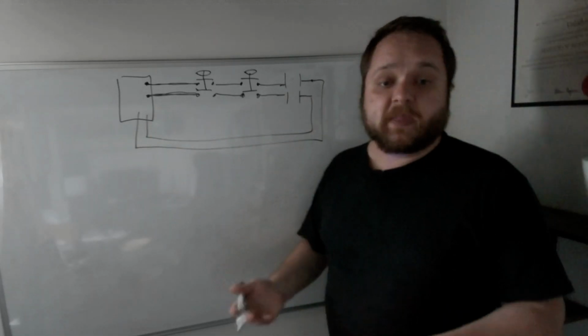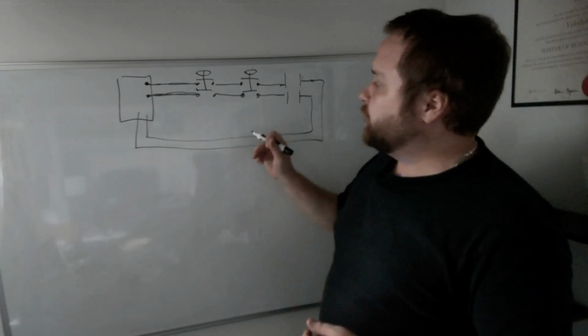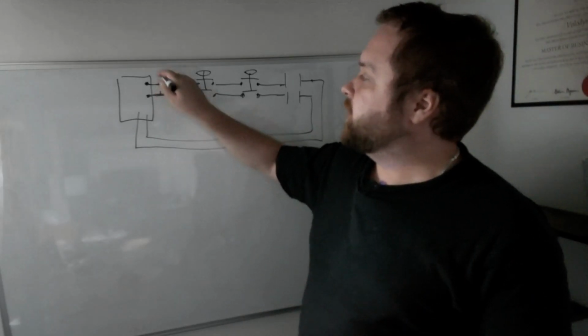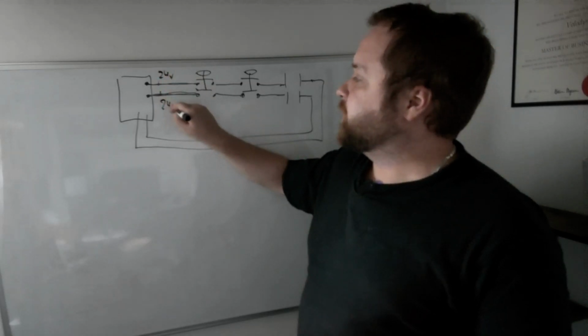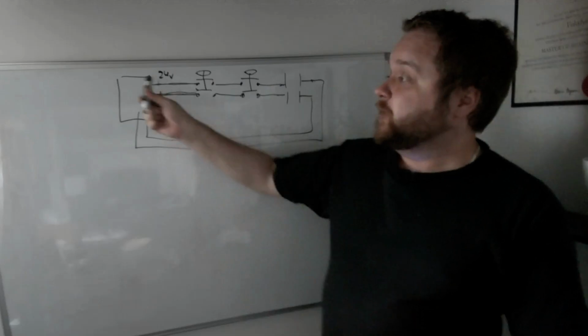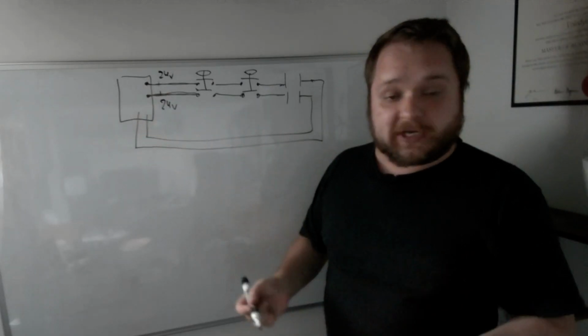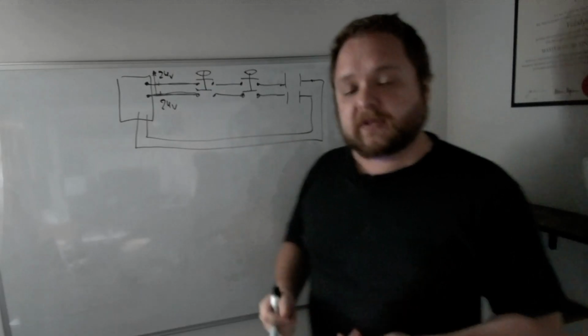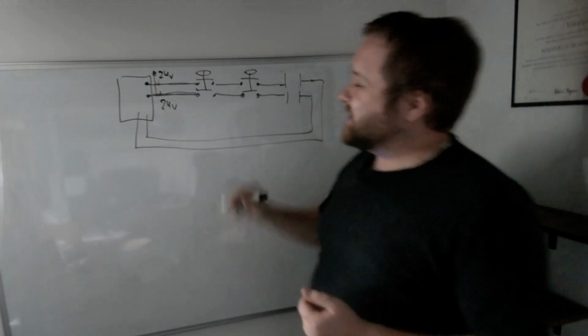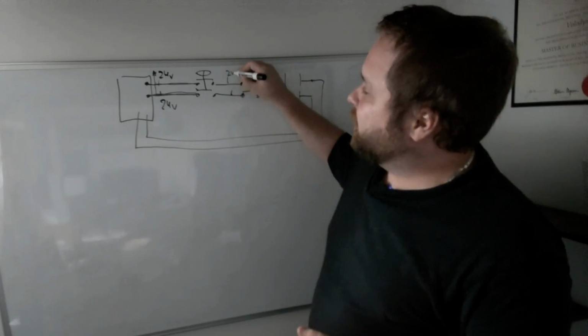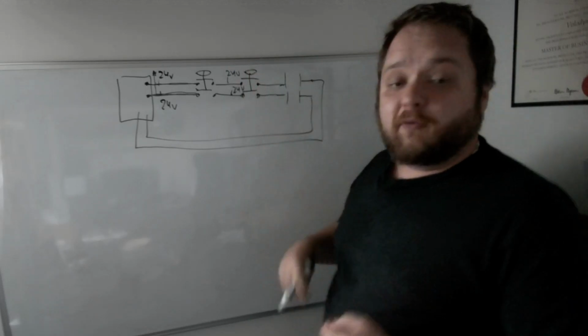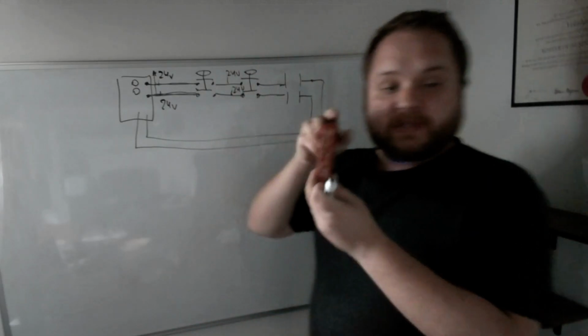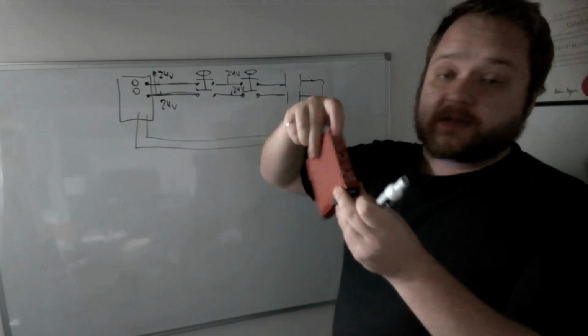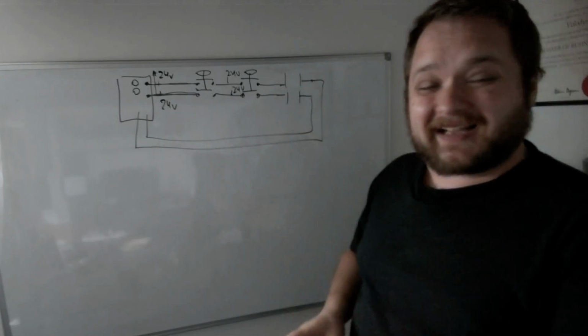This is a fairly common application and a fairly simple one, but what you're looking for here is, first of all, you're going to have 24 volts on each channel. So first and foremost, if you're troubleshooting this kind of circuit, you need to validate that you have 24 volts on each channel. A lot of times it is done internally specifically to make sure that the relay is actually working. But basically, you're going to have to check that there's 24 volts along the entire chain for the safety relay to say that both channels are okay. And a lot of times you will have a set of LEDs. I don't know how easy it's going to be seen on the actual safety relay, but basically there's going to be 2 LEDs that indicate the status of each channel.